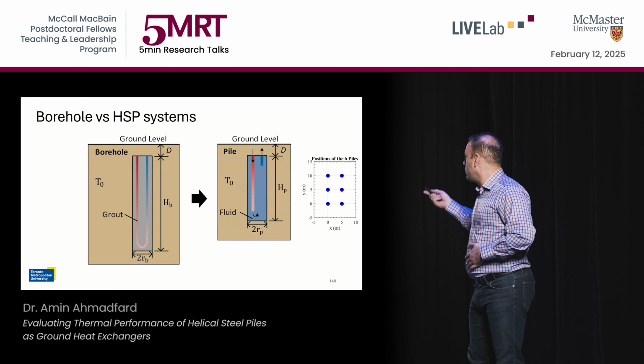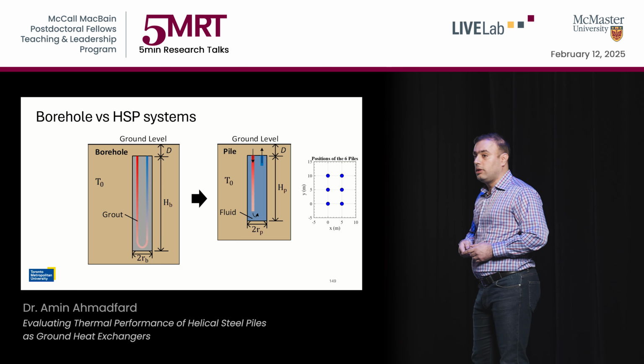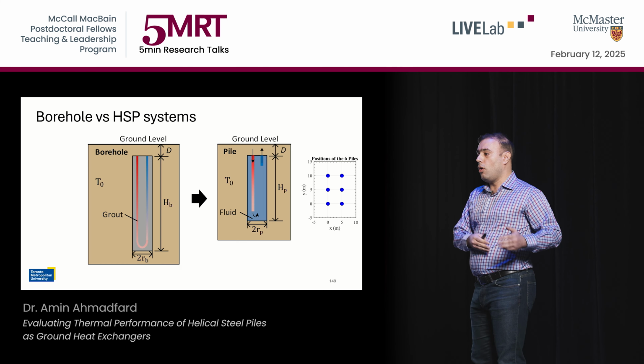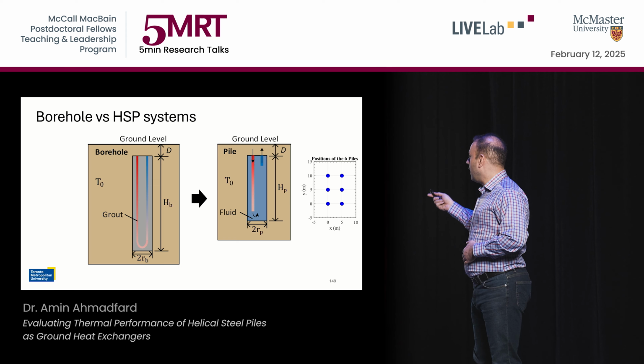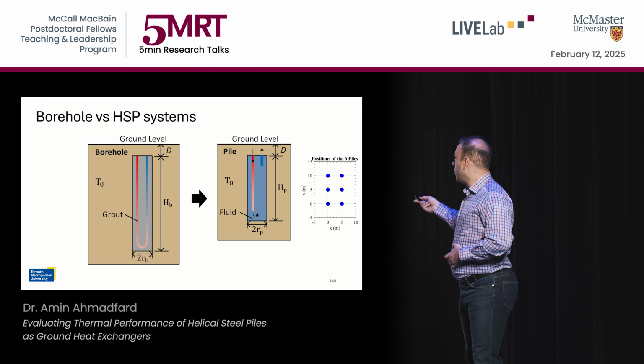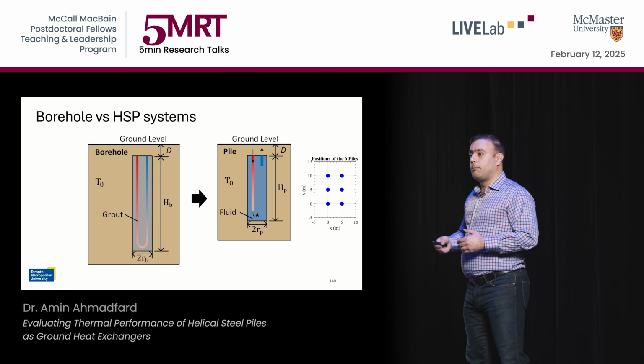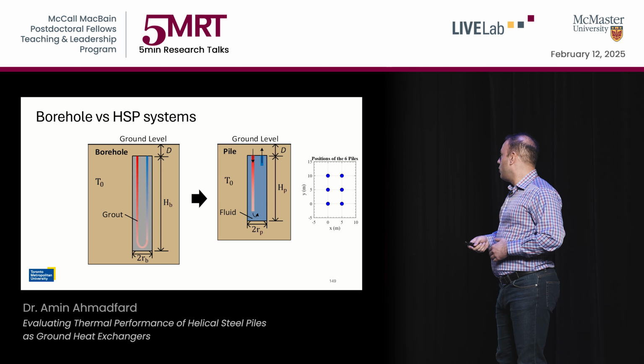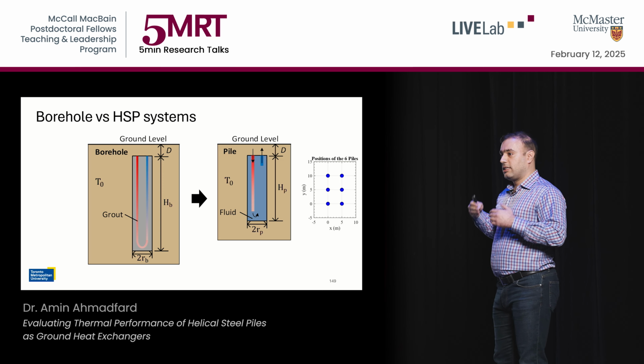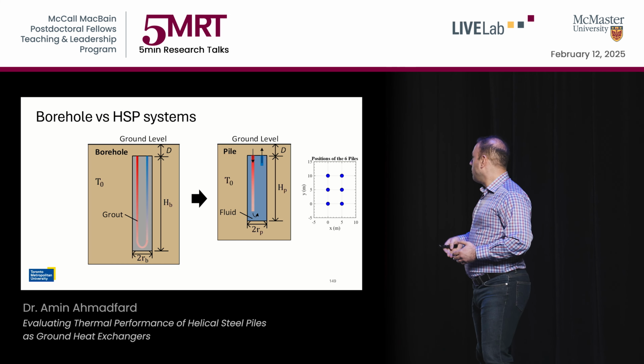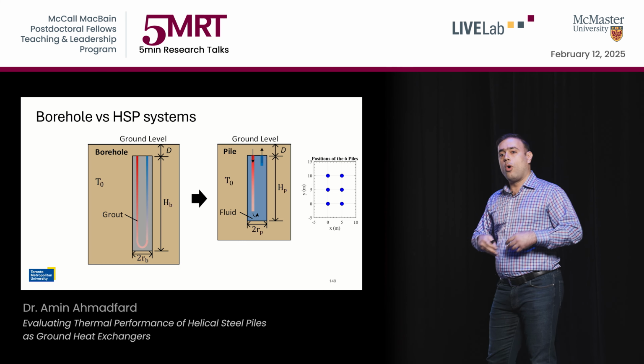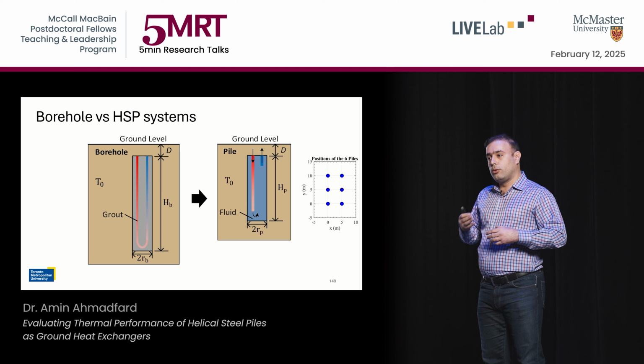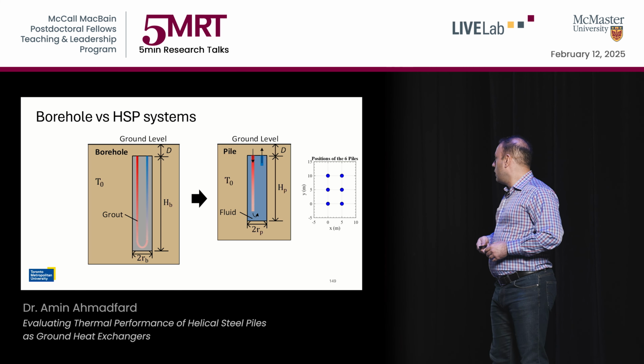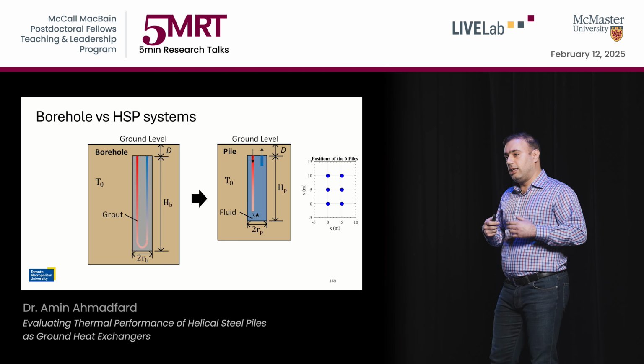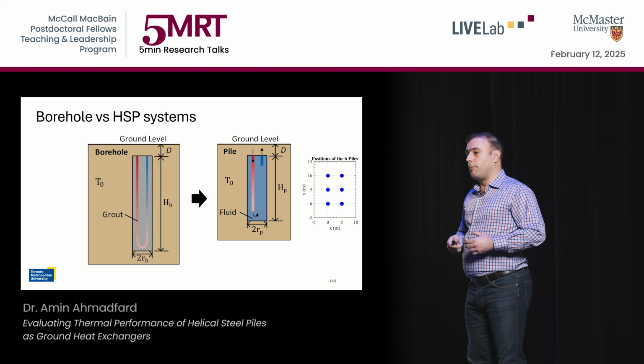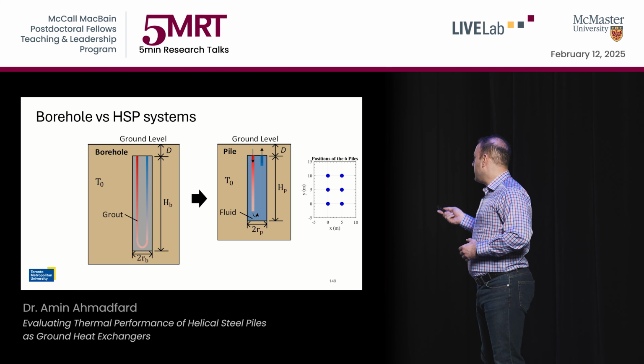I've compared two designs: boreholes versus helical steel piles. The helical steel piles are shallower, and instead of U-tubes like in boreholes, they have a pipe that sends water to the bottom of the pile, giving the water more time to come up and exchange heat with the ground. This makes them more efficient compared to U-tubes and boreholes.